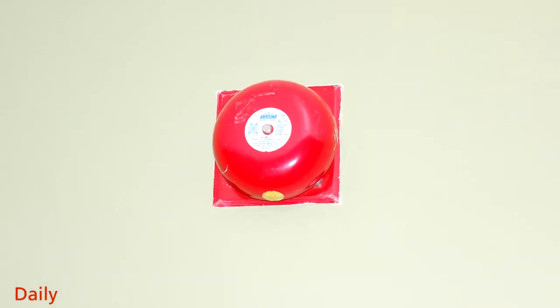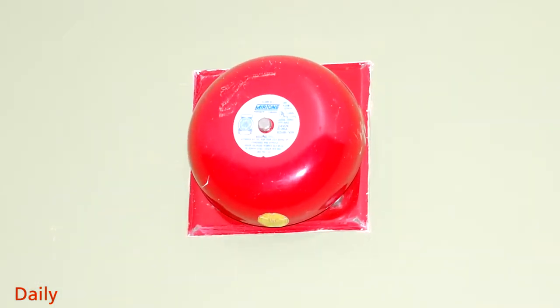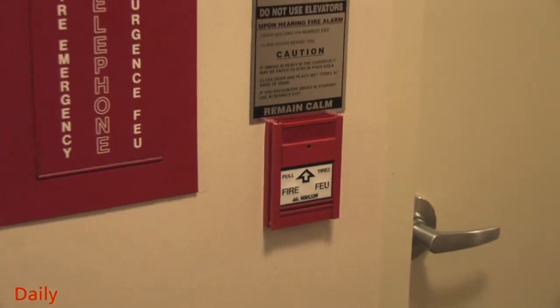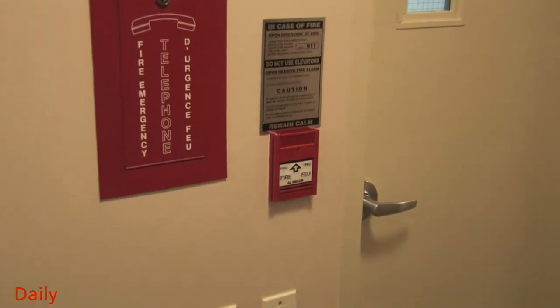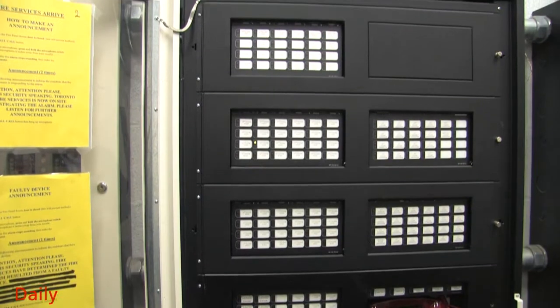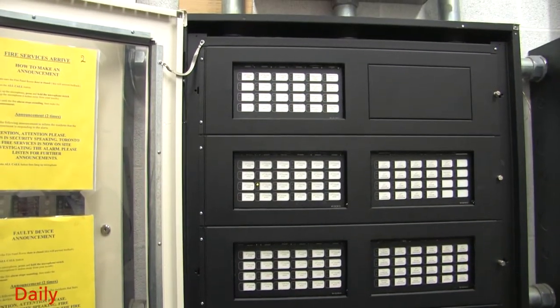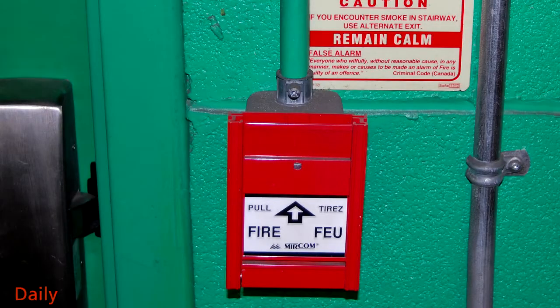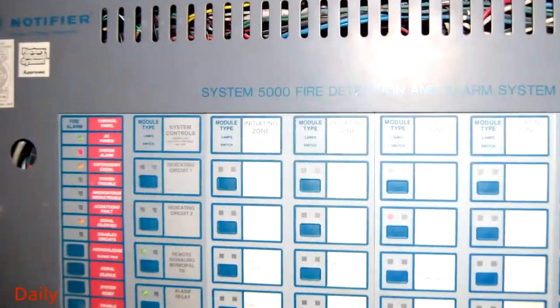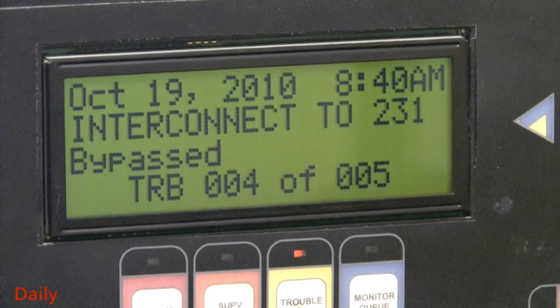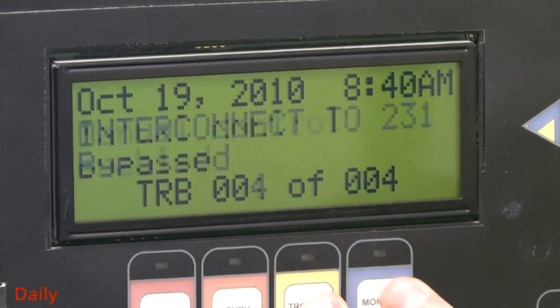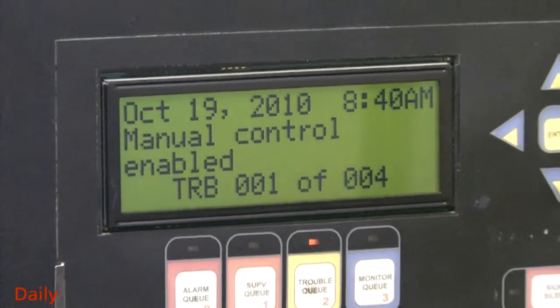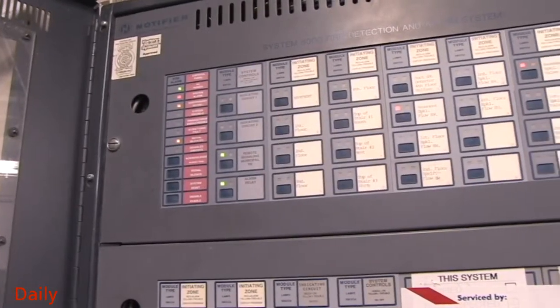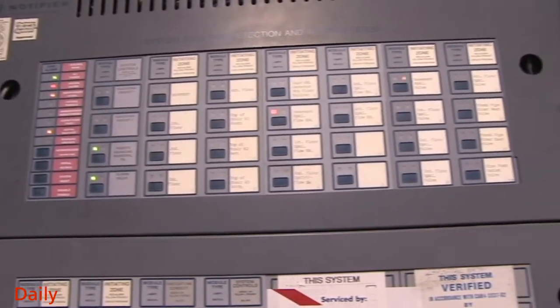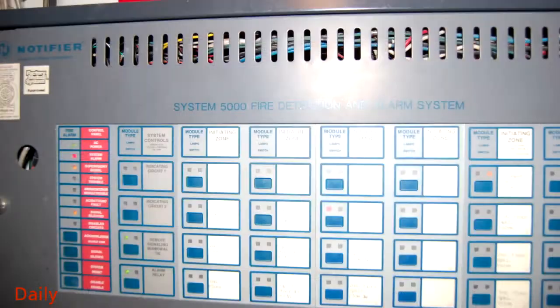Staff should make a visual check of all fire alarm and voice communication systems on a daily basis to ensure they are unobstructed. Components include the fire alarm control panel, annunciator panel, manual pull stations, heat detectors, and supervisory switches. Visually check principal and remote trouble lights on the main fire panel to ensure that no trouble is indicated on the system. Inspect the AC power on light or equivalent indicator to ensure its normal operation.